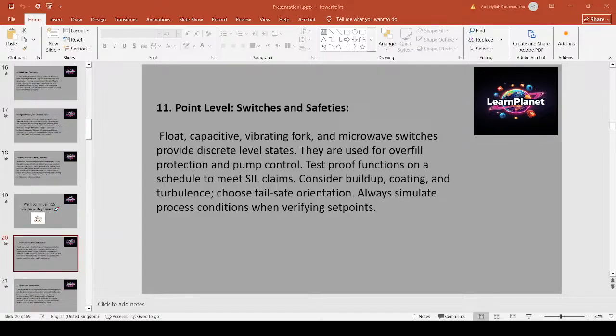Point level switches, float, capacitive, vibrating fork, and microwave, provide reliable discrete signals for low-high alarms and safety interlocks. Select based on media, coating buildup, temperature, and required fail state. Failsafe open or closed. For safety critical overfill or low-level trips, test proof functions regularly to maintain SIL claims. Consider mechanical robustness and mounting orientation relative to flow turbulence. Example: use dual vibrating fork high-level switches on a transfer tank to provide redundant overfill protection with voting logic.